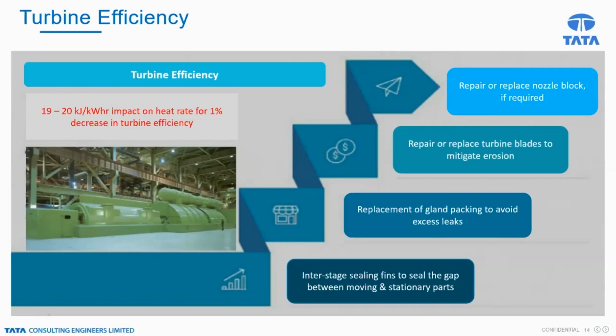So I talked about the parameters: one, improving the boiler efficiency; two, reducing the superheater and reheater spray or attemperation quantity; and third, maximizing the turbine efficiency to have a better heat rate.